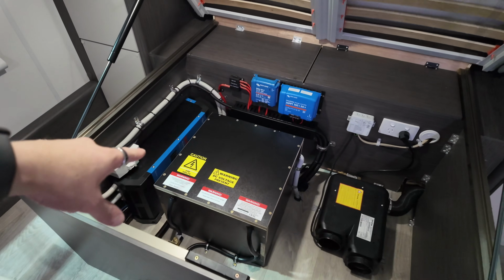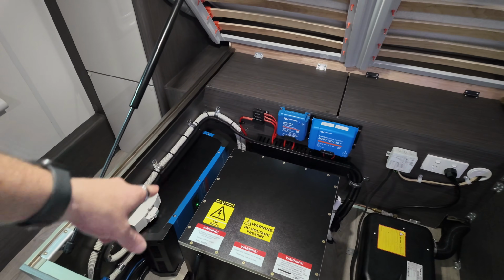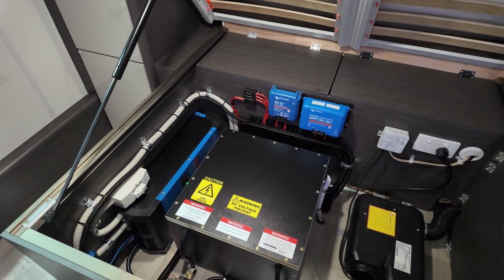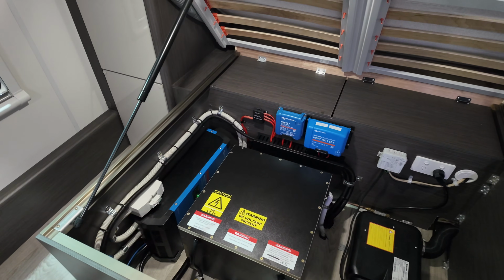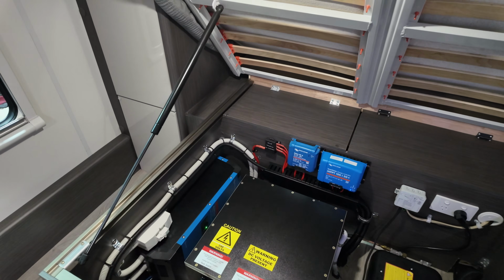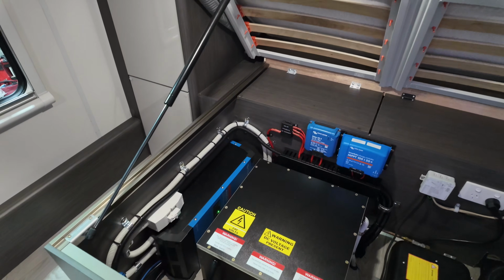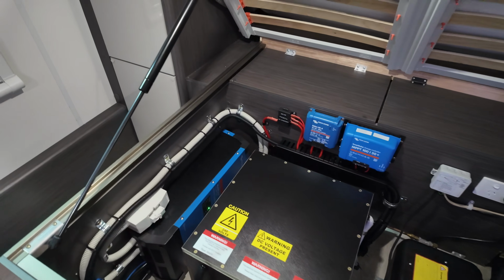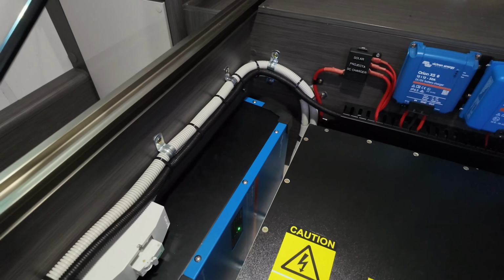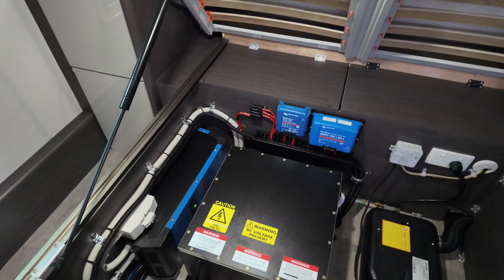In the system here we've obviously got the 3 kVA multi-plus, which we use in basically all the systems - 120 amp battery charger, 3 kVA multi - but you'll see in a bit that it can go above the 3 kVA. It's a very, very sturdy bit of kit, hence why we install so many of them. That's your 120 amp battery charger.